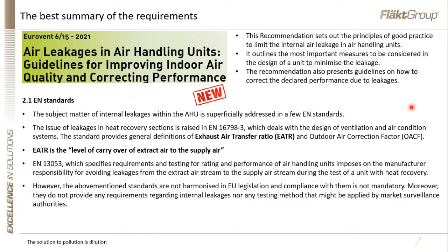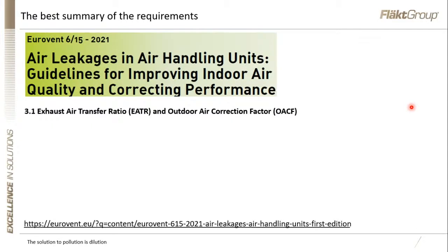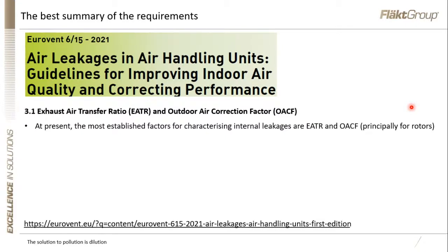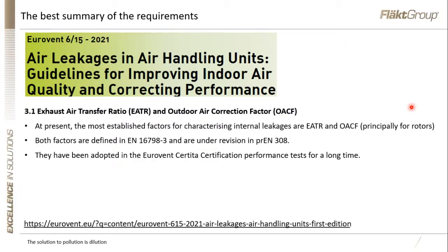So the subject of internal air leakages within air handling units is a little bit of a grey area, and there is absolutely no guarantee that some manufacturers' equipment isn't leaking internally, and there's no way of verifying that for certain manufacturers, I should stress. So further on in this particular document, it talks about exhaust air transfer ratio. At present, the established factors for characterising the internal leakages are EATR, and that's principally for rotors. And they're both defined in EN 16798-3, and they are under revision in prEN 308, which is the test standard for heat recovery devices. The PR means it's provisional at the moment. It's been published for consultation, but it's not yet a published standard. And they've been adopted actually within Eurovent's certification criteria.